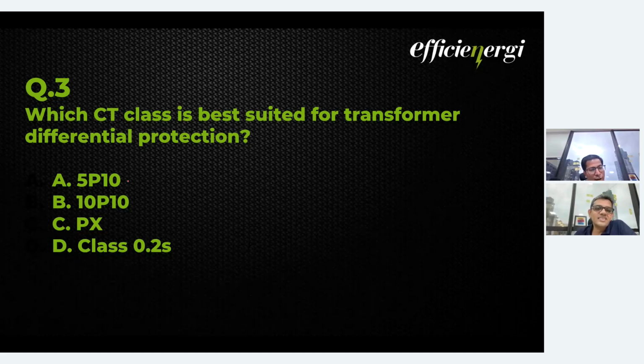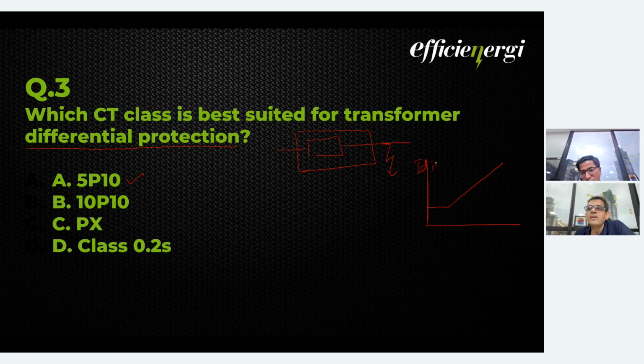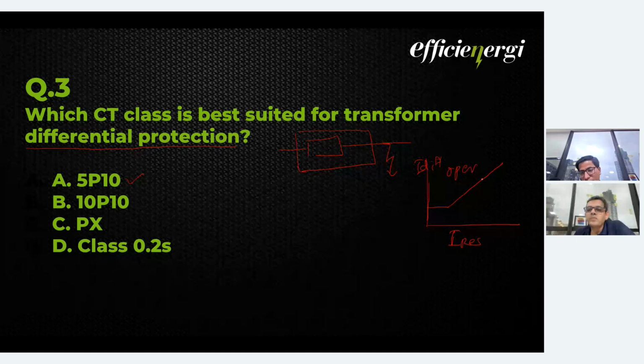So 5P10 you have answered for differential protection, because just now what I explained, the differential protection is a very sensitive protection because it is a unit protection. It should not operate on any fault which is external to the zone of protection. So it has to be very sensitive for lower faults. If you know the differential protection, how it works: this is I differential, and there is an I restrain current. So here it should operate, and here it should restrain.